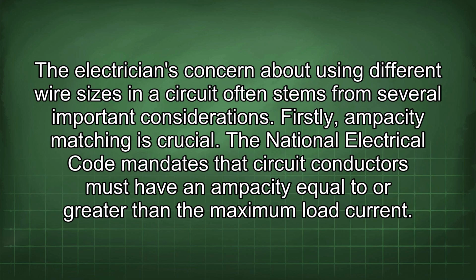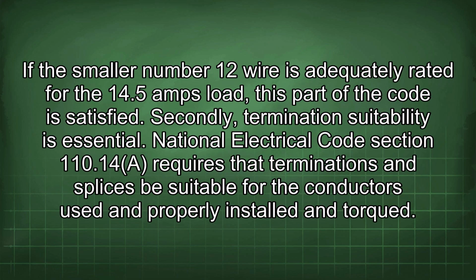The electrician's concern about using different wire sizes in a circuit often stems from several important considerations. Firstly, ampacity matching is crucial. The National Electrical Code mandates that circuit conductors must have an ampacity equal to or greater than the maximum load current. If the smaller number 12 wire is adequately rated for the 14.5 amp load, this part of the code is satisfied. Secondly, termination suitability is essential.